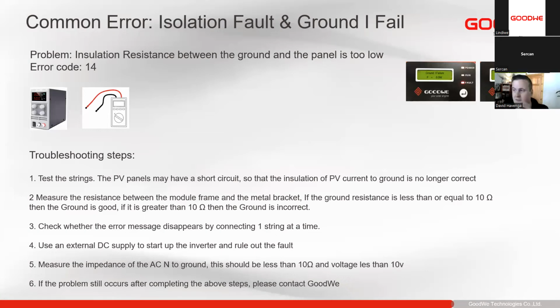We now need to move on to test the strings, then we can do each string one by one. And that is just one of the quick ways to do the testing. Also, we need to measure the resistance between the module frame and the metal bracket to make sure our grounding of our PV modules is correct. So it should be less than 10 ohms.